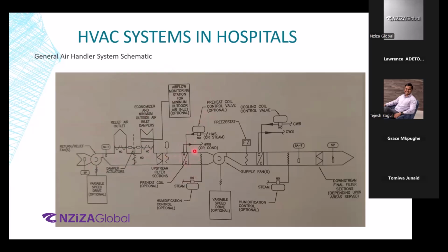We have the heating coil, also sometimes called the preheat coil. We might also have some steam jets. Steam jets are usually used to maintain the relative humidity. If the air that we are getting at this point is too dry and we want to maintain a certain relative humidity, we can have steam injected into the airstream so that it increases the relative humidity of that air. Okay. Of course, we have the supply fan over here.